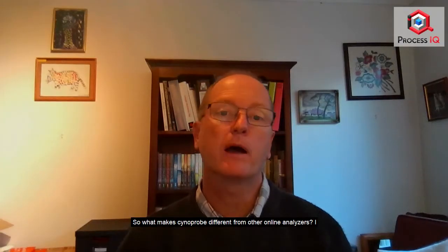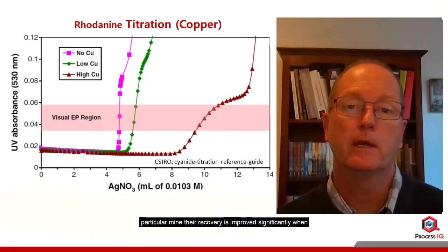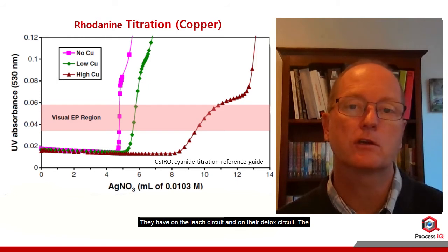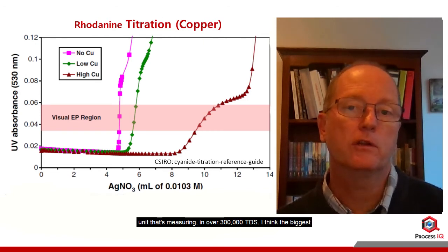So what makes Cynoprobe different from other online analyzers? I think the thing that makes Cynoprobe different is its ability to measure the available cyanide for leaching gold. Some mines that have very high copper struggle with recoveries because of the available cyanide. At one particular mine, their recoveries improved significantly when they used the Cynoprobe readings — they now have five analyzers, on the leach circuit and on the detox circuit. The unit also has fewer interferences from things such as thiosulfate. Salt also does not affect the readings — we have one unit that's measuring in over 300,000 TDS.